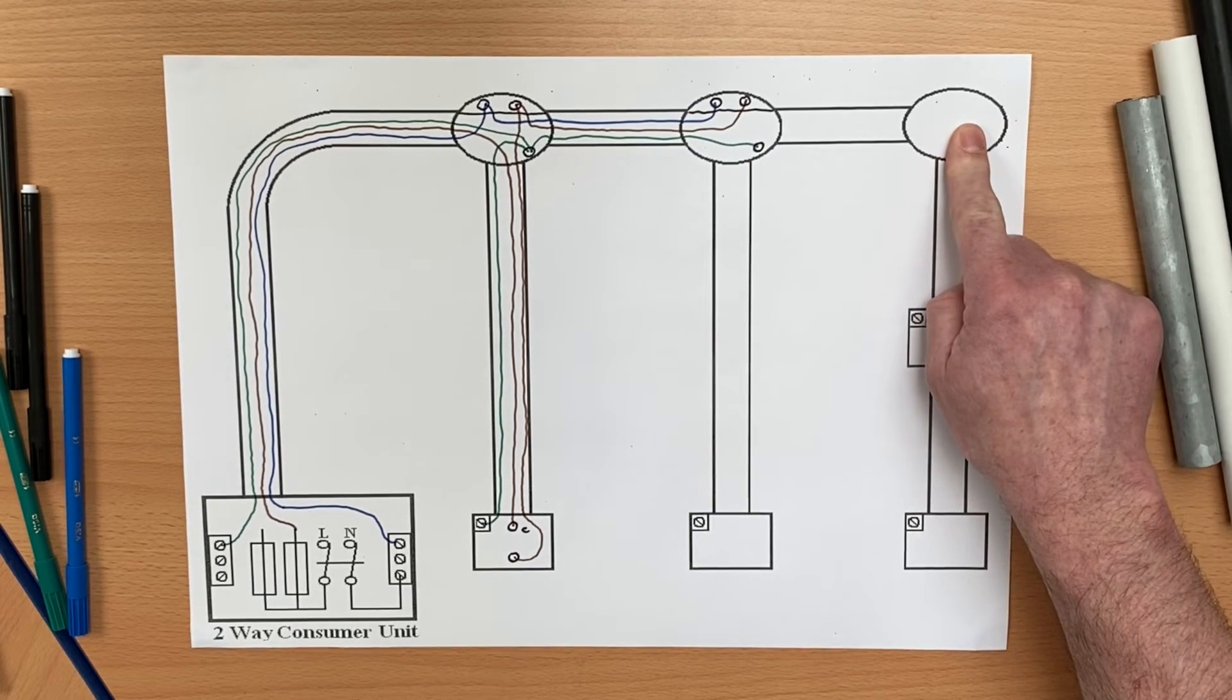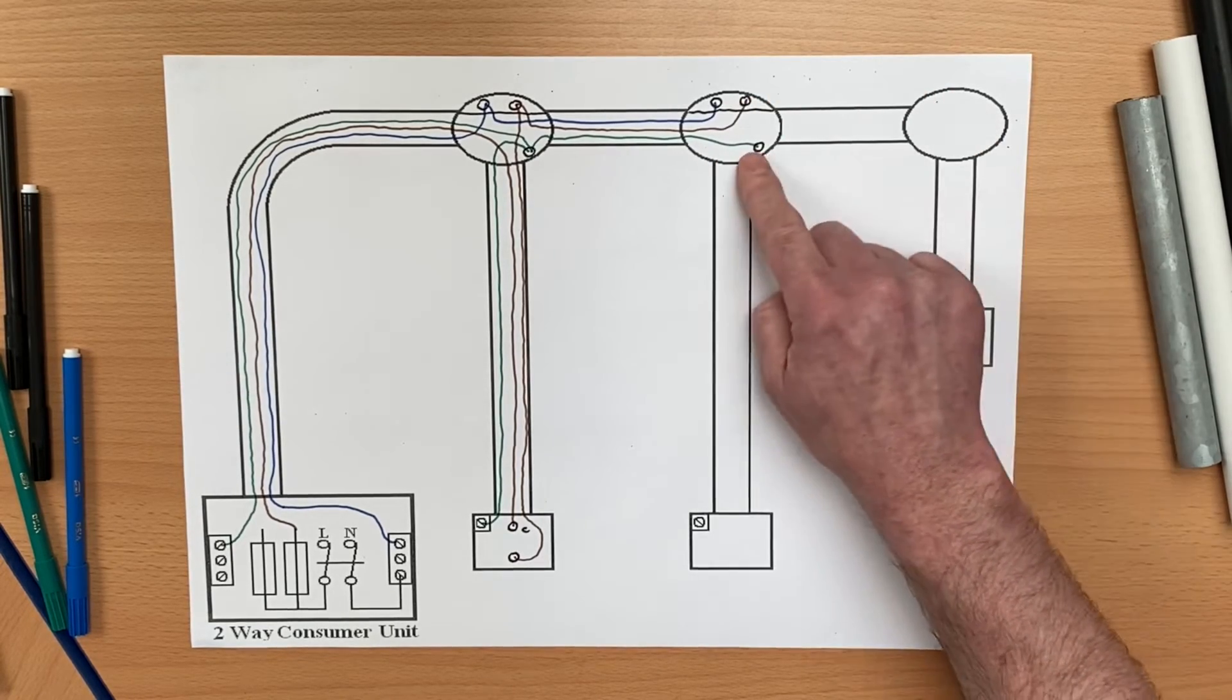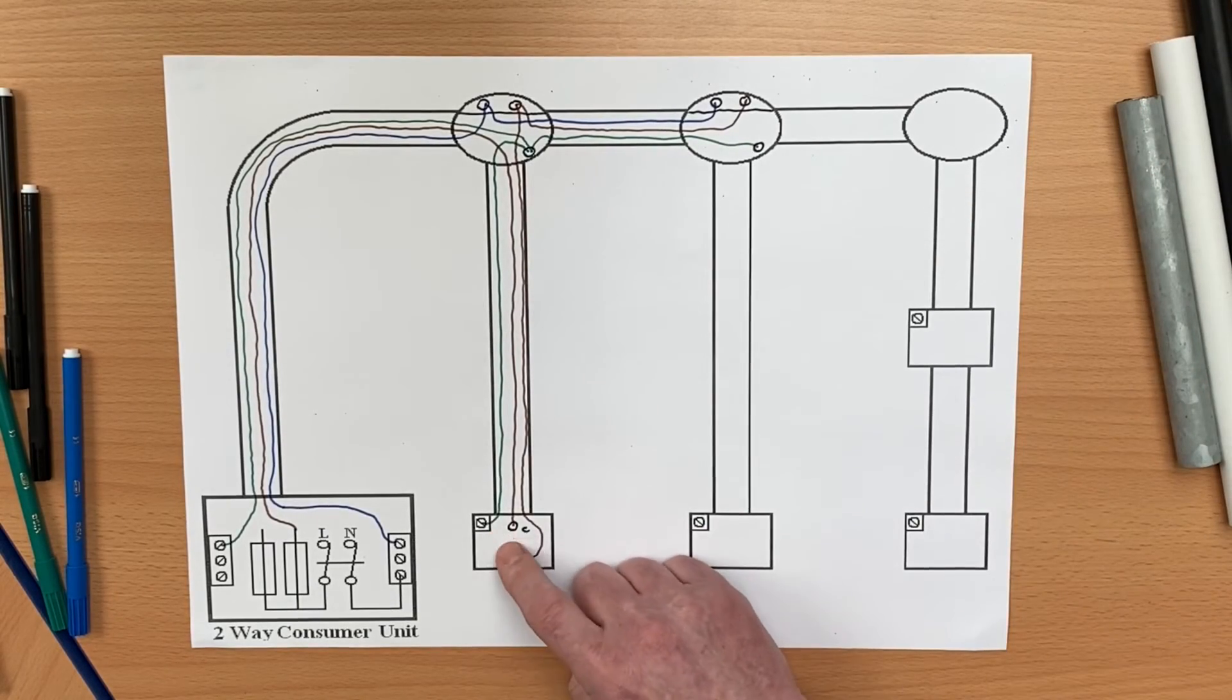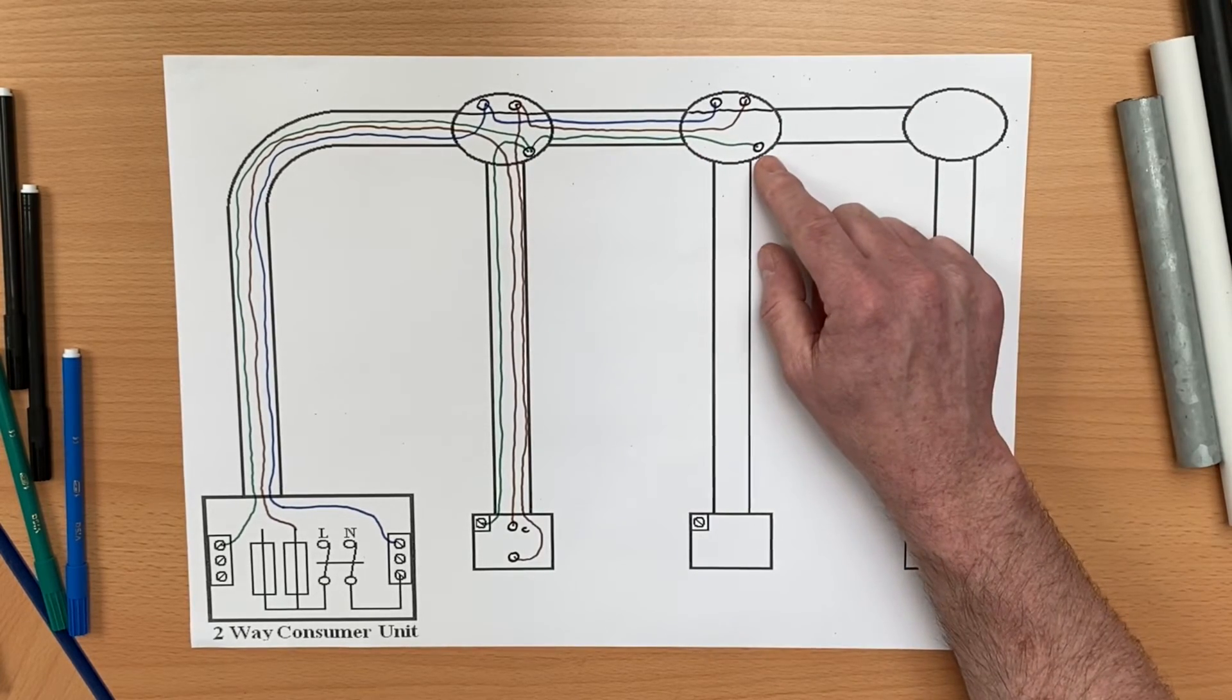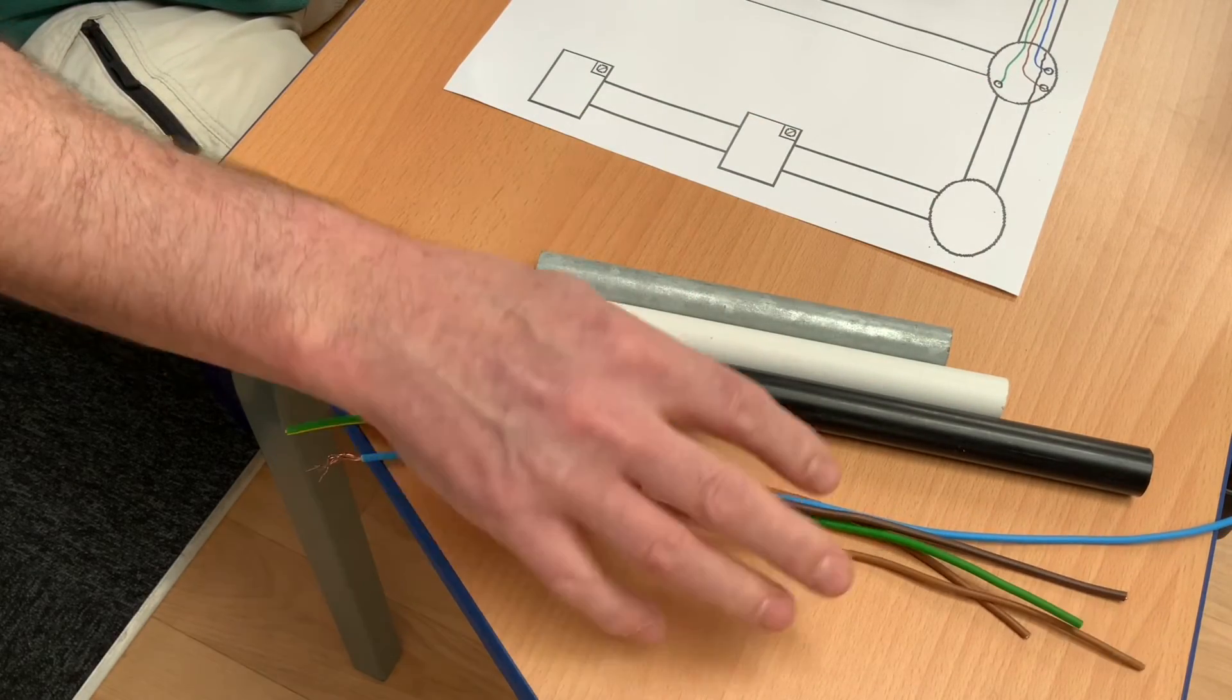It might be that you want more lights. How do we do that? We continue the process on. Let's say we were putting this light on as well. We drop a neutral across, the switching line across, and the CPC across in these PVC single cables to the next lighting point, meaning that this switch will turn on this light, this light, and the process can continue. This is building on the knowledge from previous videos in this series using the conduit looping method.